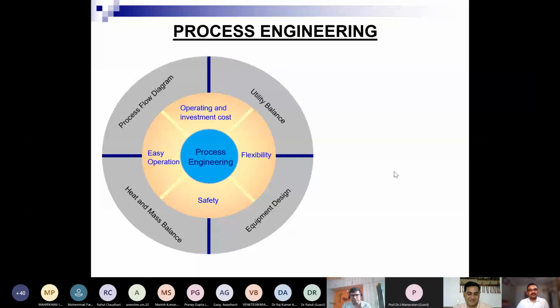As per my experience, typically in refinery technologies, customer asks for 50 to 60% turndown. If the turndown has to be for long term operation, then we add a process case in addition to the normal 100% case. Typically we design hydraulics for 50% turndown, and about 10% higher for pumps and compressors, for rotating equipment. That's what we do for the hydraulic basis.